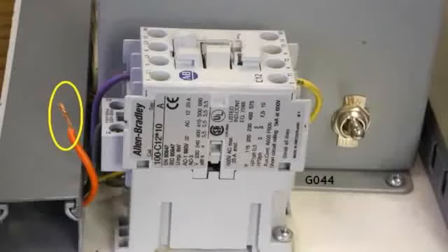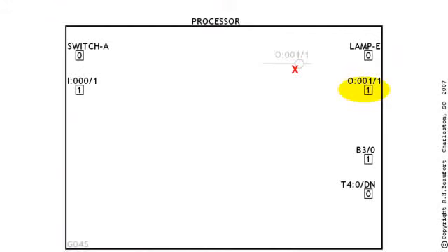The old "works like a relay coil" explanation is a misguided effort to water down the OTE for beginners. The problem is that most classes taught that way never get past the beginner stage. The beyond-beginner way to look at the question in this example is like this. Now that we've taken away the OTE instruction, there isn't anything left in the program to tell the processor what to do with that bit. The processor won't change the status of a bit without an instruction. So the correct answer is that the bit will keep its 1 status.